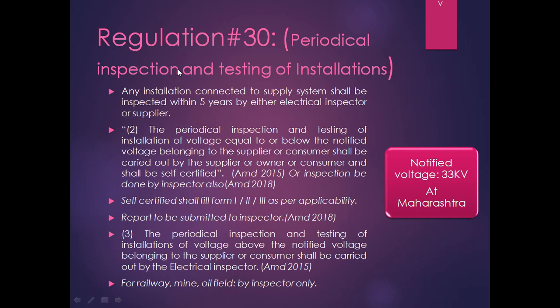Now regulation 30, another very important regulation from a statutory point of view. This regulation is regarding periodical inspection and testing of installation. First, let me read the statement. Any installation connected to the supply system shall be inspected within 5 years either by the electrical inspector or the supplier. The periodical inspection and testing of installations of voltages equal to or below the notified voltage, belonging to the supplier or consumer, shall be carried out by the supplier or the owner or consumer and shall be self-certified, or inspection can be done by the inspector also.